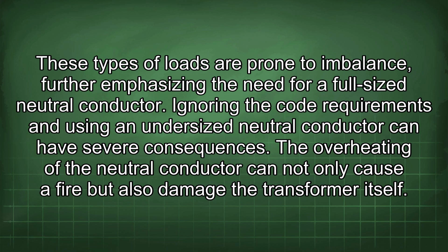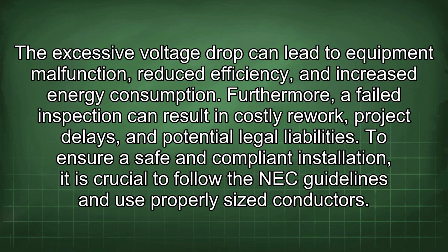The overheating of the neutral conductor can not only cause a fire but also damage the transformer itself. The excessive voltage drop can lead to equipment malfunction, reduced efficiency, and increased energy consumption. Furthermore, a failed inspection can result in costly rework, project delays, and potential legal liabilities. To ensure a safe and compliant installation, it is crucial to follow the NEC guidelines and use properly sized conductors.